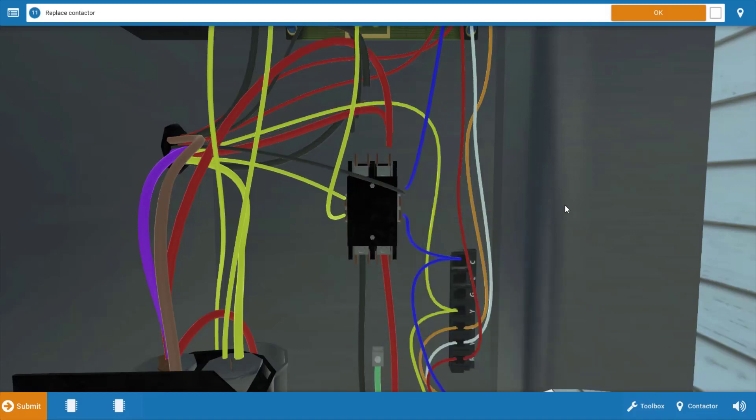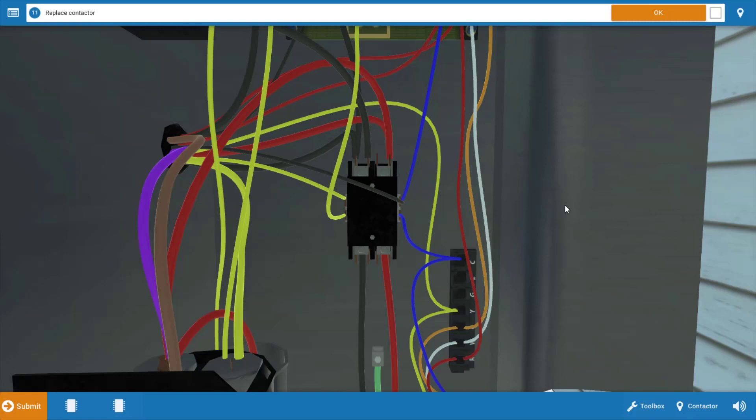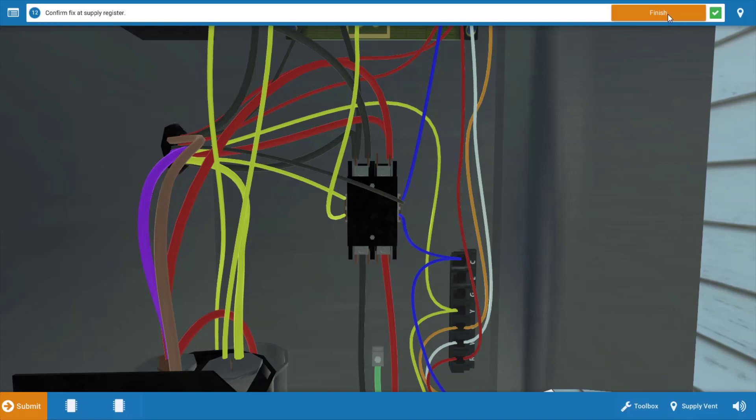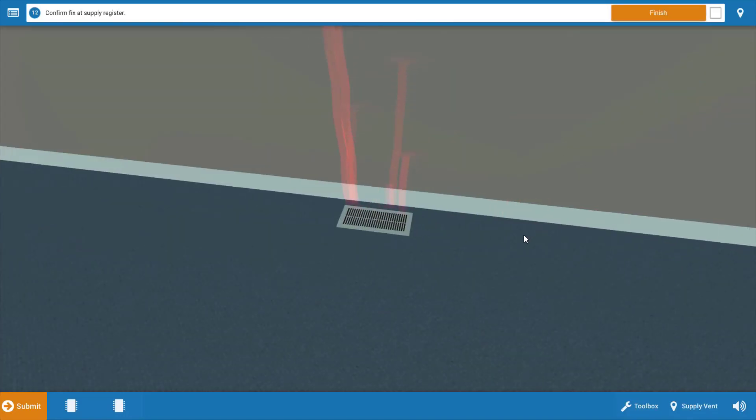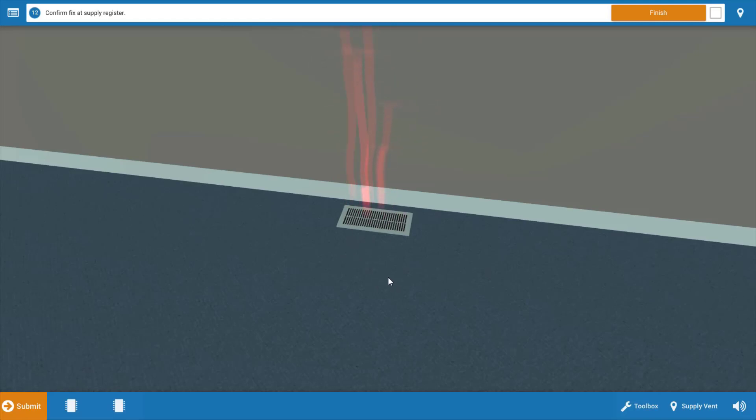We need to reestablish power back to the unit and observe one full cycle of operation to determine all loads are operated properly. Again, I would pull the indoor air filter and replace it if it's dirty. And last but not least, we're going to go up to the space and just verify that warm air is being received through the registers. And based on the graphic here, it in fact is receiving warm air. So we've solved our problem.